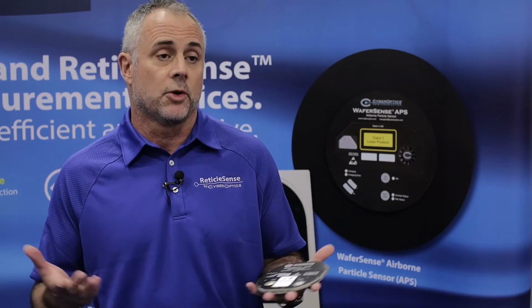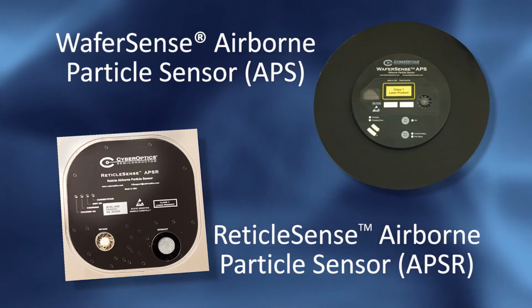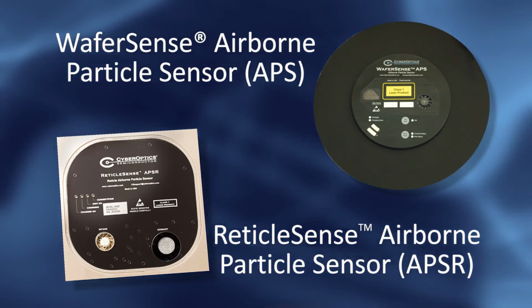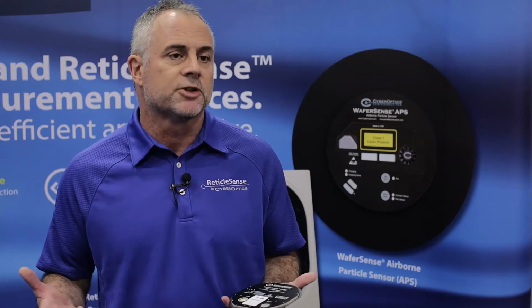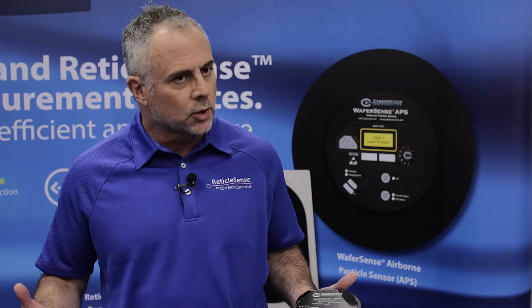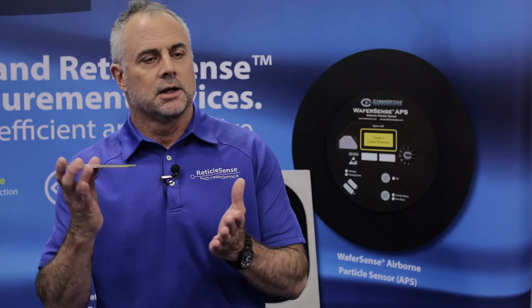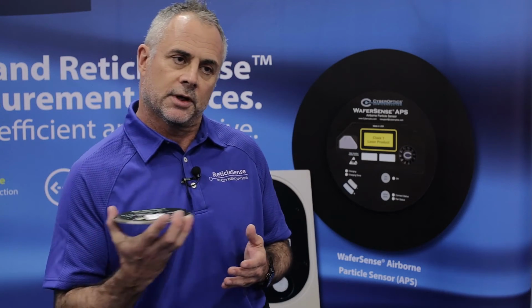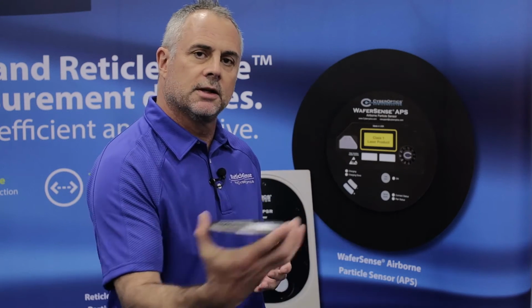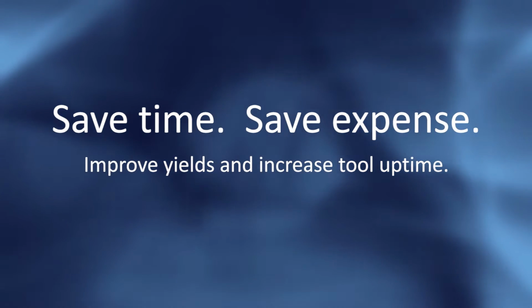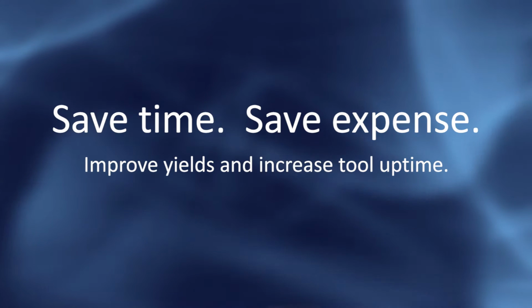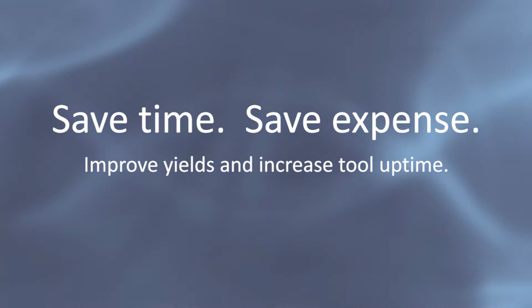There was a need to do calibrations and measurements more quickly, to do them under actual vacuum conditions that most of the process tools use, to save data, to have repeatable results, to basically save time. Rather than the tool being opened up and vacuum broken and all the time-consuming effects of breaking vacuum and tearing the tool apart, the WaferSense devices go from the front of the tool at the FOUP, through the front end, through the vacuum lock, transfer chambers, load locks, process chambers, and typically 85% time savings, higher accuracy, improved yield.